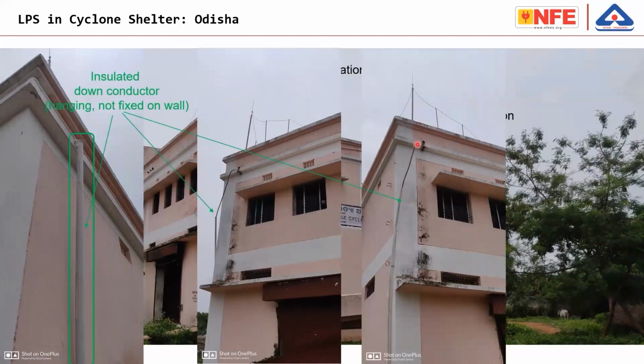And this project, for example, protecting this building, the lightning protection alone is worth probably 40, 50 lakh rupees because these are special wires, high voltage insulated conductors. And these conductors have to be fixed to the wall of the building at every half meter, whereas the wires are completely hanging. If the lightning hits, due to mechanical forces, all this installation will be thrown away. It is not going to exist.